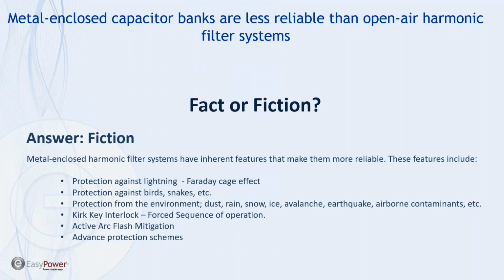Inadvertent operation of the system is a common cause for failure. A metal-enclosed system is typically key interlocked. We force a sequence of operation. We force a sequence to get into the equipment, and therefore we prevent misoperation, which can lead to failure.